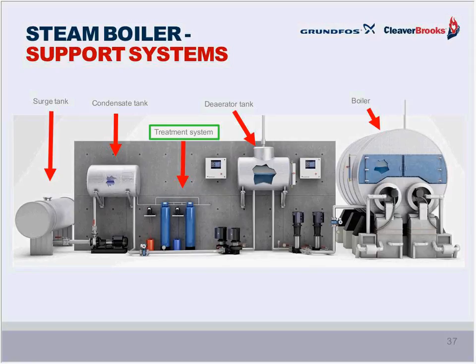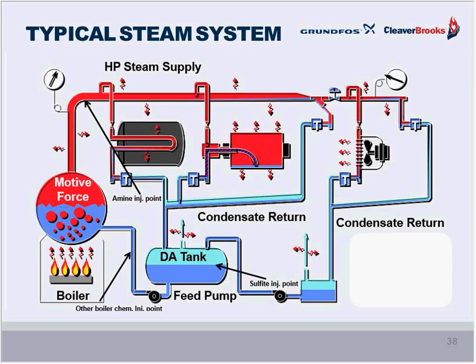So as with a typical steam boiler setup and its components, we acknowledge the need for chemical treatment pumps and systems. Chemical injection can occur at a variety of points in the boiler system, as we will see right here. In this diagram, you've seen it a couple of times, but here's another look at it with injection points. The first, up at the top left, we see the amine injection in the steam line, exit boiler in the upper left-hand corner. This line will typically range from perhaps 1 to 300 psi. Later, we will discuss how pressure will impact pump selection.